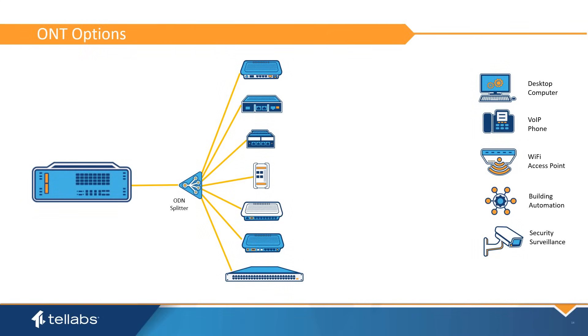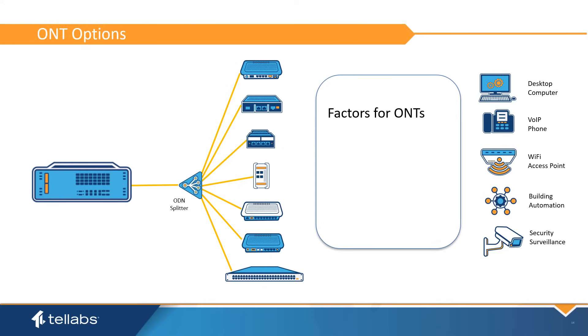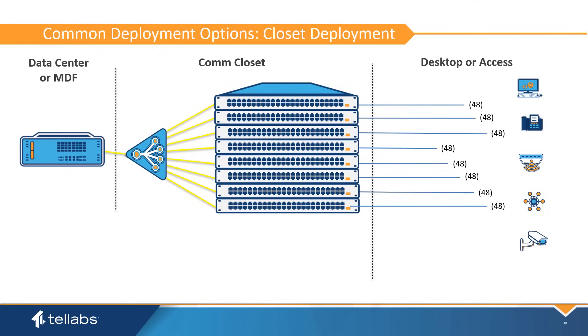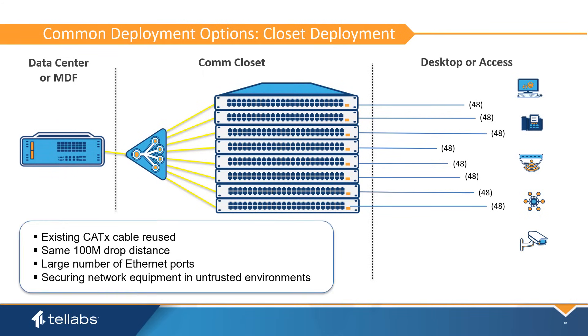One of the unique features of optical LAN is the flexible deployment of the ONT. ONTs have been designed for a variety of installation options. Factors that may determine what type of ONT to use include service type, building codes, security, economy, density, and location. ONTs are not network switches and do not need to be secured in the network; however, it may be advantageous to deploy them as you would an access switch. By placing the ONT in the equipment room, existing CAT-X cable can be reused, a higher density of ports can be installed where needed, and network components can be secured in untrusted environments.